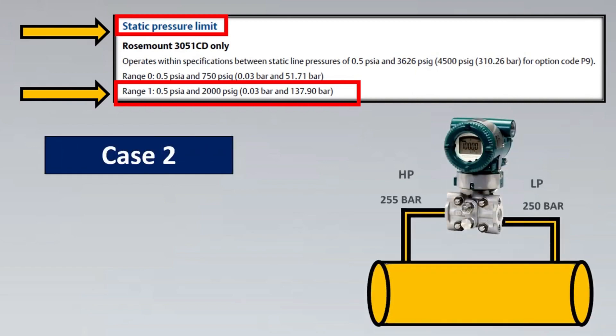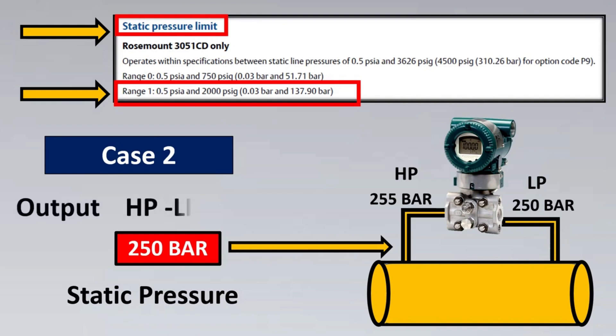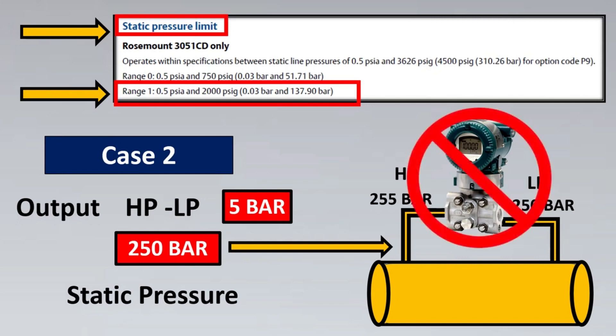The static pressure limit states that for Range 1, the maximum static pressure it can experience is 137 bar. But in our second example, the pressure hitting commonly on both legs was 250 bar. The static pressure was too huge, and if you had used the 3051CD for that case — even though the differential output of 5 bar fits your DP range — the transmitter would not be able to sustain this.